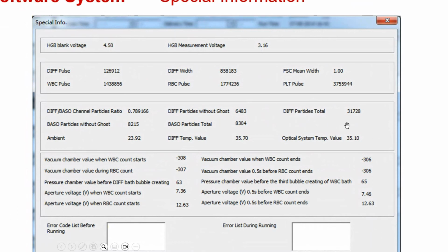Here, it is the total particles that entered the flow cell. But of course, not all of these particles are WBC. So here you see 31,000. This excess is mostly maybe some RBC ghost, debris, platelets, and so on. But among this, only 6,483 are recognized as WBC because their scattergram, their FS and SS information, fall in those population regions. Okay?